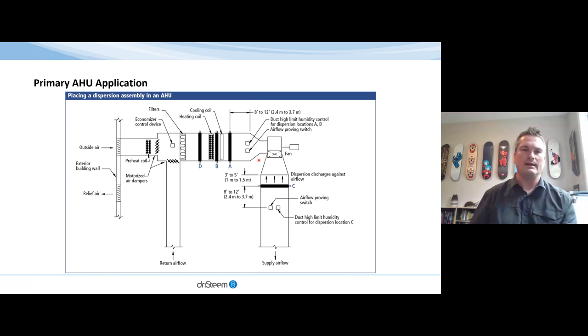Another method, if we're looking at adiabatic and using high pressure, is that we may want to have that set up after the heating coil to use that heat energy to absorb the atomization of that moisture quickly before the cooling coil. What typically happens with adiabatic is that as we get closer to the saturation curve, it becomes more difficult to add moisture. It makes it very difficult to hit saturation using an adiabatic system. So at the cooling coil, we may not be drying out the air nearly as much, but we do need to consider the distance between the heating coil and the cooling coil when looking at an adiabatic solution. Also, we can look at applying it within the duct in a more localized space, or after a VAV box, if that is the type of application.